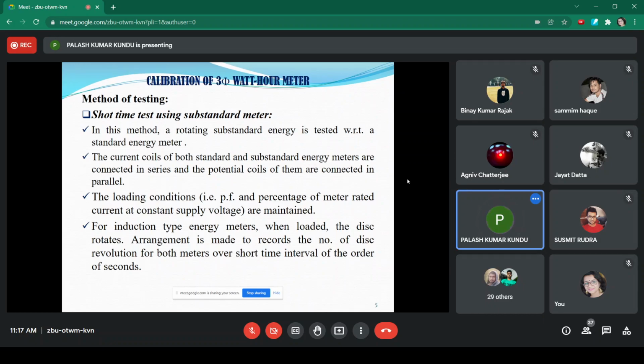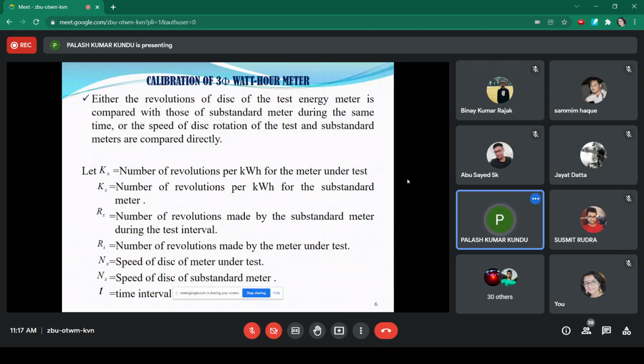In the short time test, the arrangement is made to record the number of disc revolutions for both meters, that means the substandard meter and the test meter, over a short time interval of the order of seconds. In our laboratory experiment, there are different types of testing method. One is called the short time test using the substandard meter, following these conditions of the experiment, and the results are calculated according to these parameters.